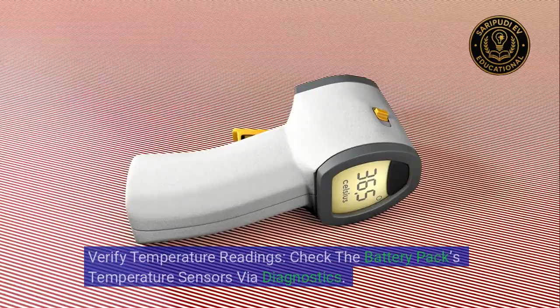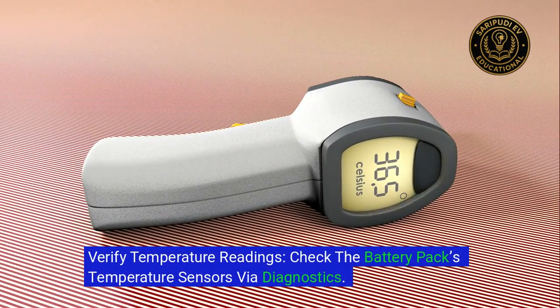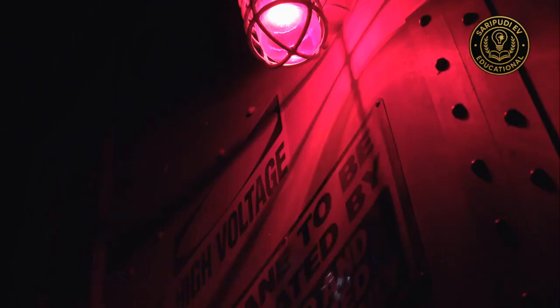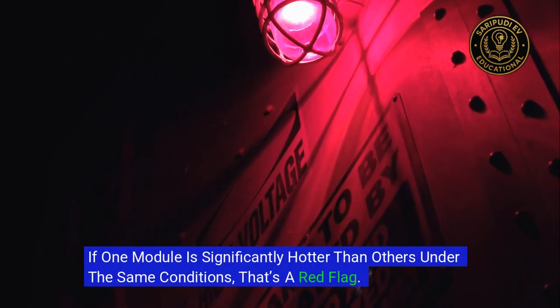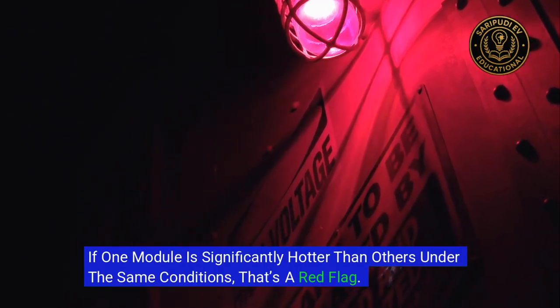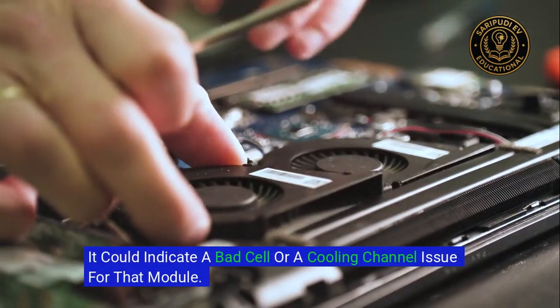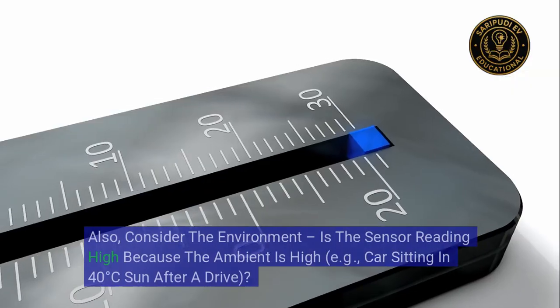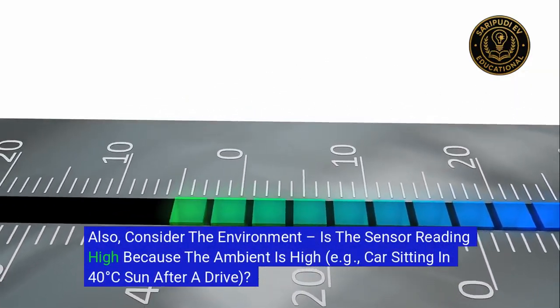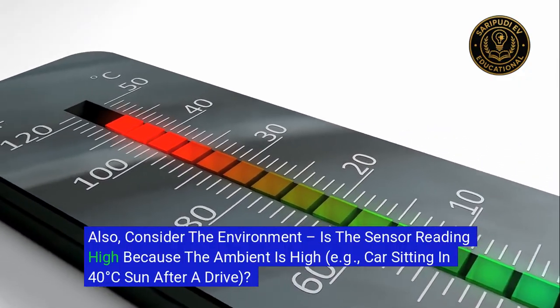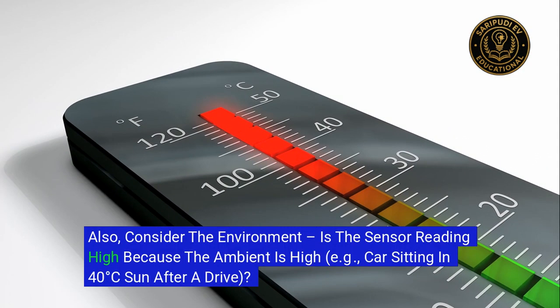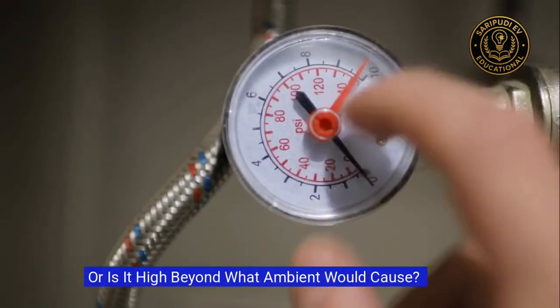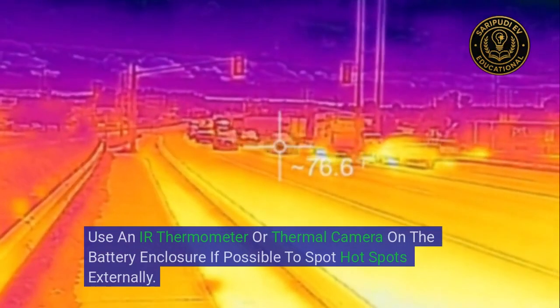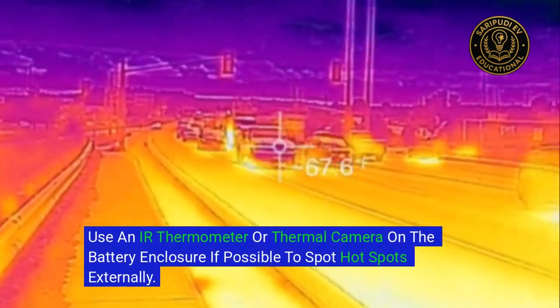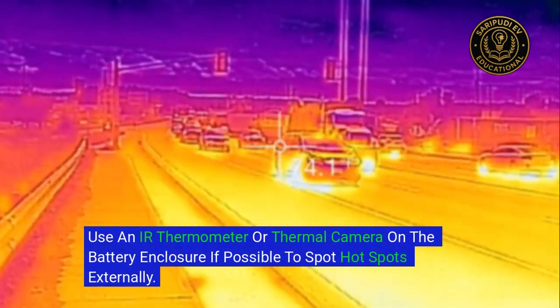Troubleshooting steps: verify temperature readings, check the battery pack's temperature sensors via diagnostics. Compare readings across the pack. If one module is significantly hotter than others under the same conditions, that's a red flag. It could indicate a bad cell or a cooling channel issue for that module. Also, consider the environment. Is the sensor reading high because the ambient is high, e.g., car sitting in 40 degrees Celsius sun after a drive? Or is it high beyond what ambient would cause? Use an IR thermometer or thermal camera on the battery enclosure if possible to spot hotspots externally.